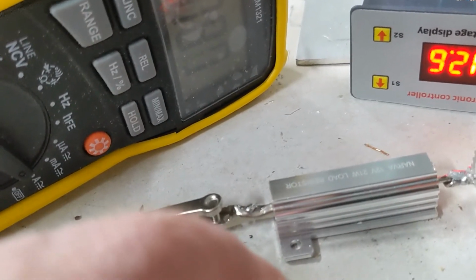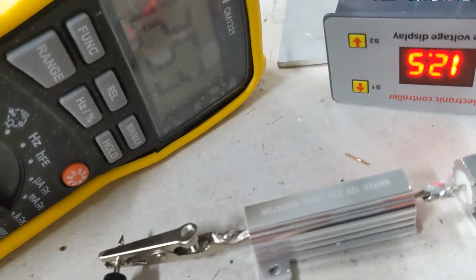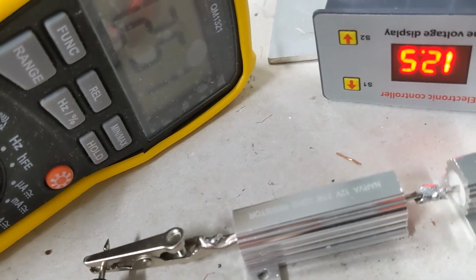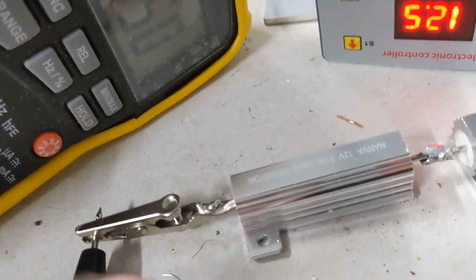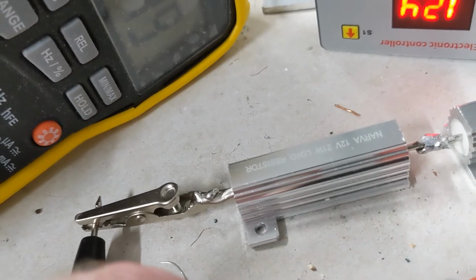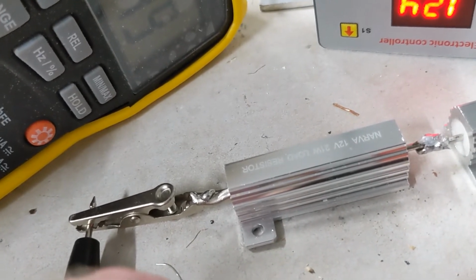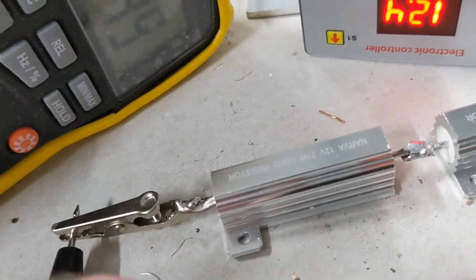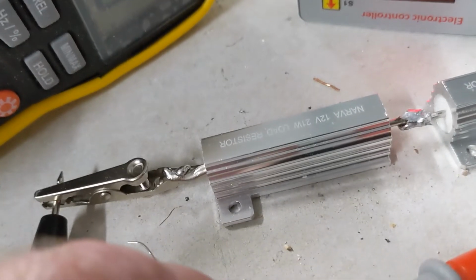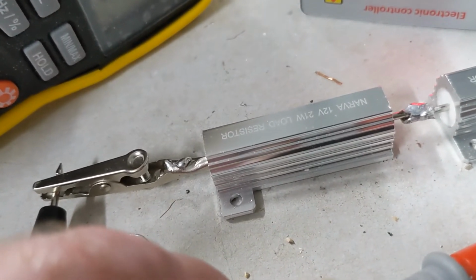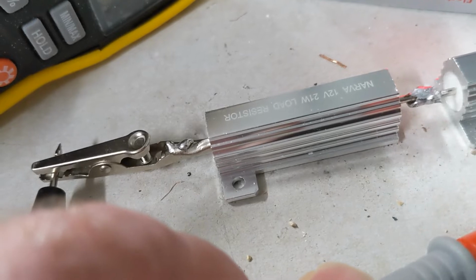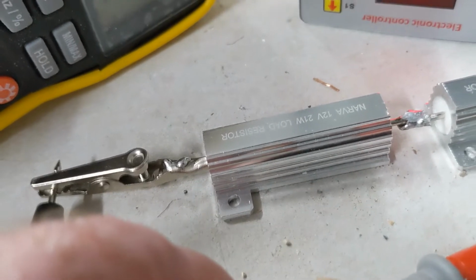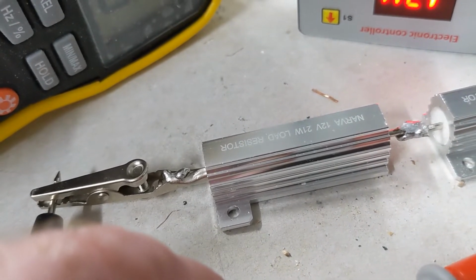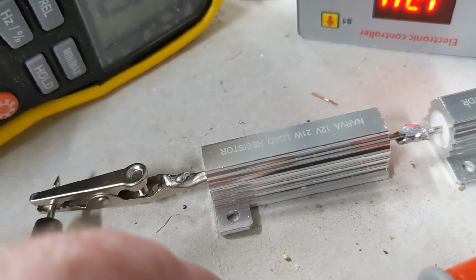Here we go, and we're getting 1.253 amps, and our voltage sag is not so bad. We're dipping to 12.4, but that's what we were at before, and I think that's probably sustainable for the period until the battery drops below its current low voltage cutoff rating. So we'll just see how much power we used.